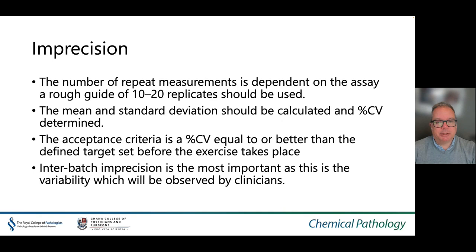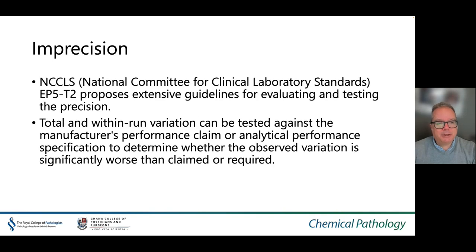The number of repeat measurements depends on the assay; as a rough guide, at least 10 to 20 replicates should be used. The mean and standard deviation should be calculated, the percent CV determined, and the acceptance criterion is that the CV is equal to or better than the defined target set before the exercise. Interbatch imprecision is the most important as this is the variability observed by clinicians. The NCCLS proposes extensive guidelines for evaluating and testing precision, enabling determination of total and within-run variation.